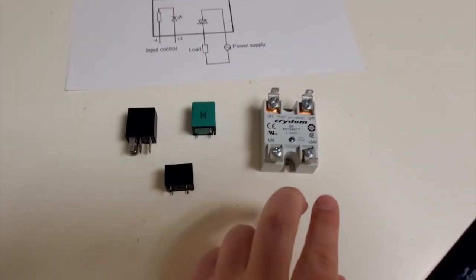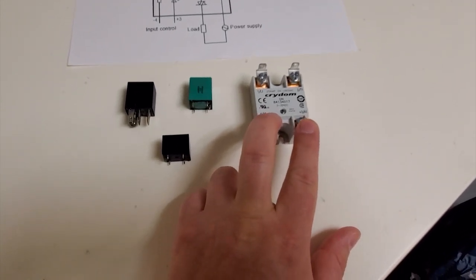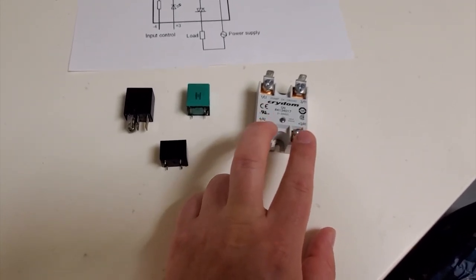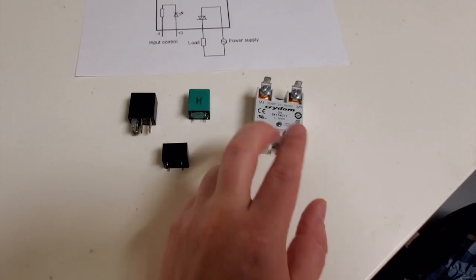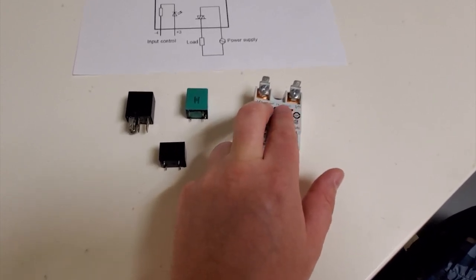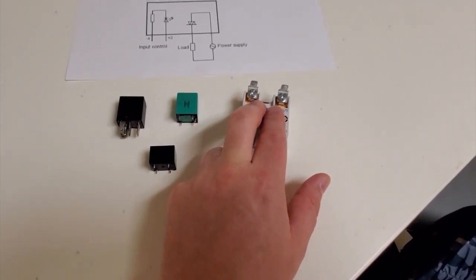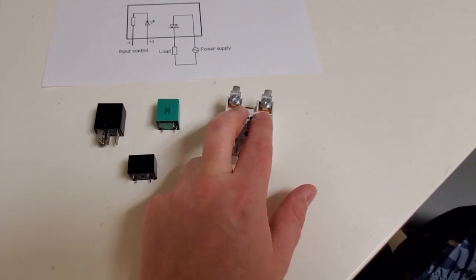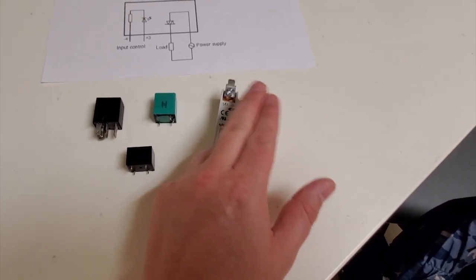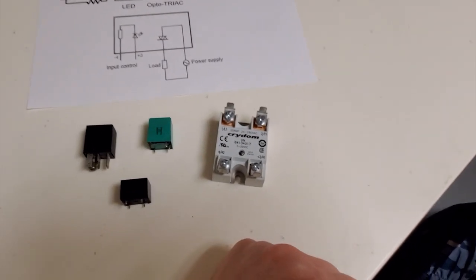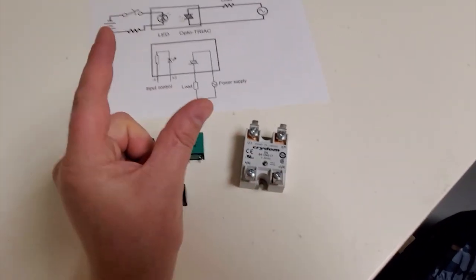So that's how you troubleshoot them. You're going to check voltage on this side to make sure you have voltage. And then on this side, you're going to check voltage to make sure that you only have about a half a volt to two volts difference between these two pins. And that will tell you if it's actually a closed circuit or not.